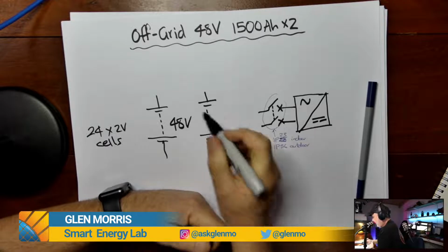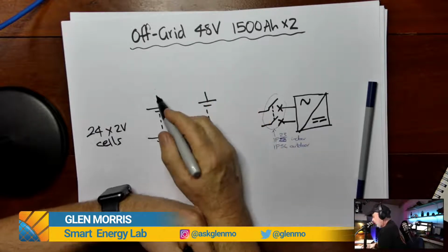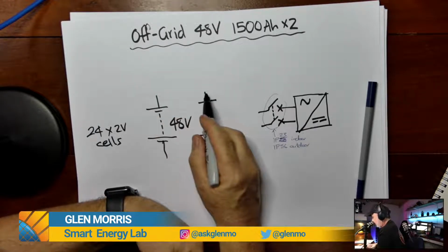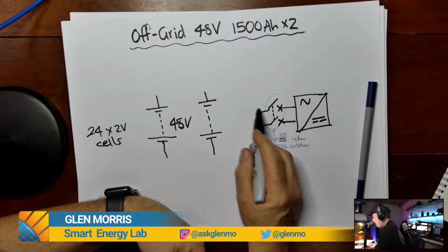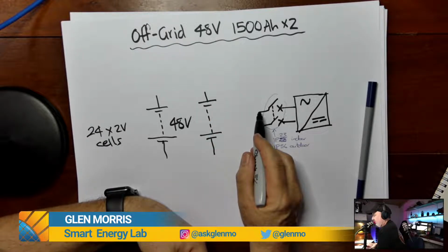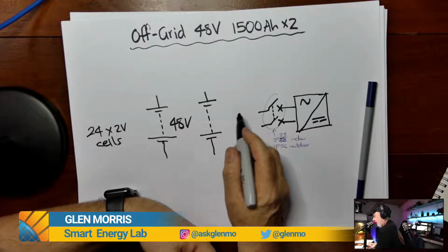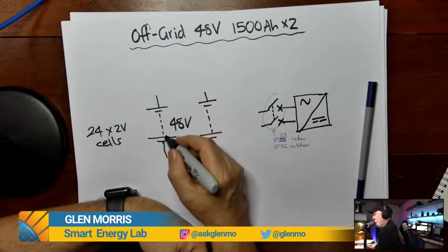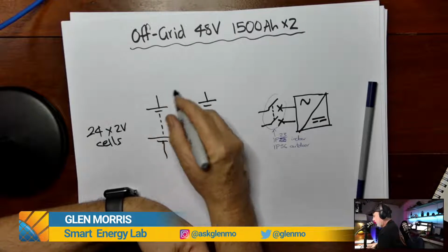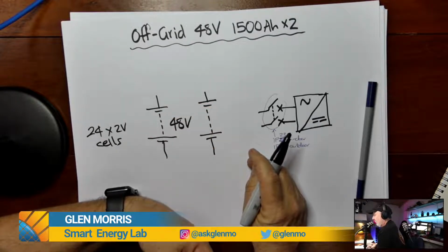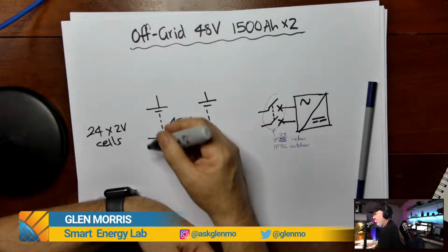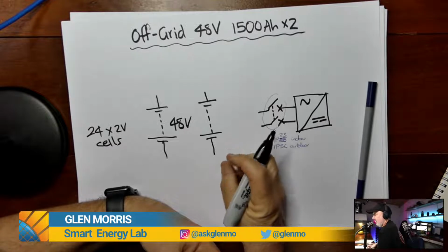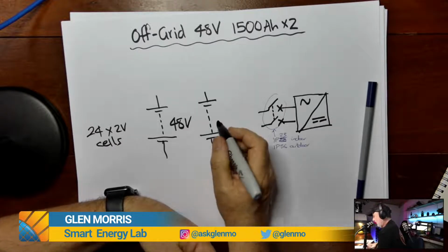The other thing that's changed too is we used to be able to connect those two strings of batteries in parallel straight to the inverter, but that's not the case anymore. And the reason for that is a very good one, which is that when you have a fault in one string of batteries, it can source current to the other string of batteries, or vice versa, and therefore you can have a very, very high short circuit current within a battery bank, and nothing's going to stop it except the thickness of the cable, so likely a fire.